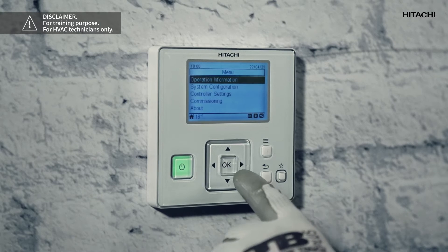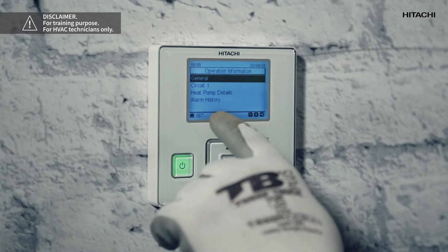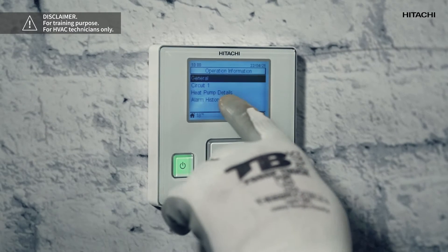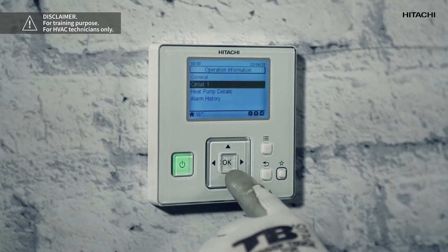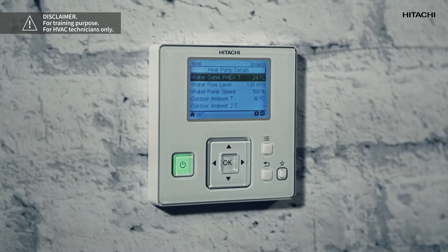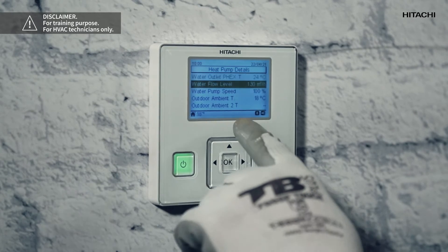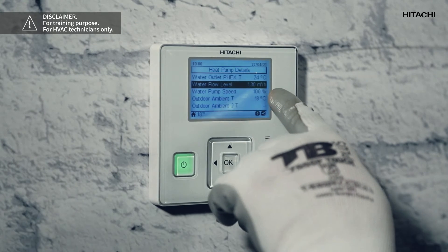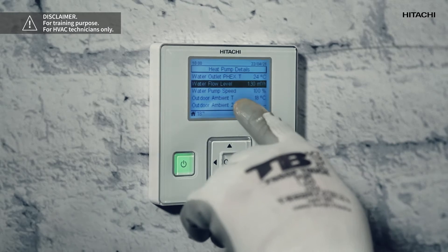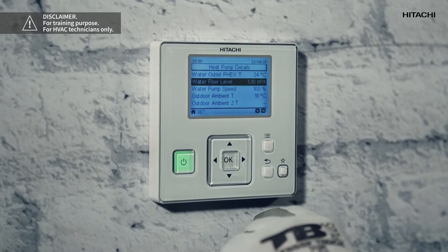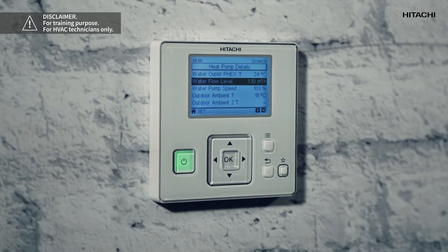The first two causes happen when there is no flow in the equipment. The first thing we're going to do is observe the flow of the pump, so that you can check how much flow there is. If the flow rate is less than the minimum required, then the problem is hydraulic. If there is no flow, the problem may be on the PCB, in the pump itself, or there may be an obstruction.